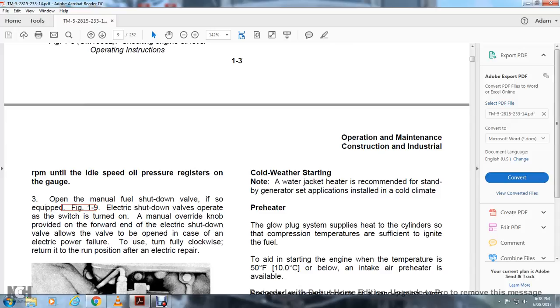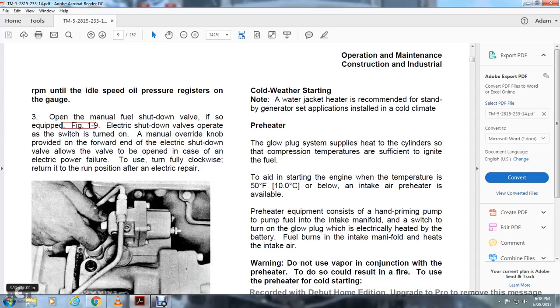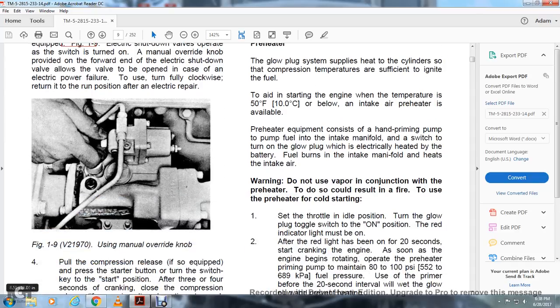Open the manual fuel shutdown valve. If equipped with electronic shutdown valves operated with the switch turned on, a manual override knob at the forward end of the electrical shutdown valve allows the valve to be opened in case of an electrical power failure. Turn it fully clockwise. Return it to position after the electrical repair. Figure 1-9, using a manual override knob.